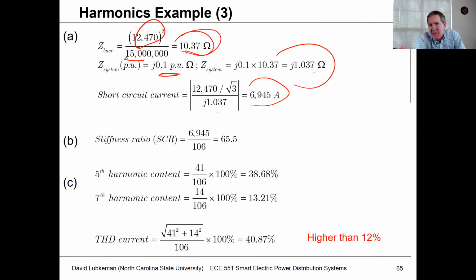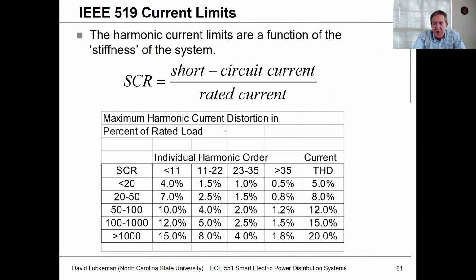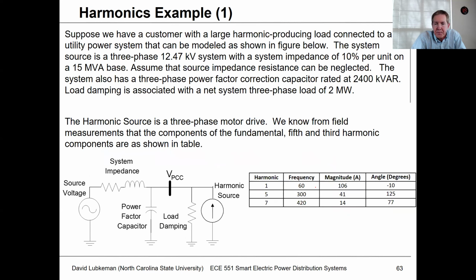So if I have a load injecting 106, the stiffness factor is this short circuit current divided by 106, which is 65.5. So whenever going into the tables to get the limits, I'm going to look at the values corresponding to 65.5, which fall into this range here. What this does is give me the limitations on the individual harmonics and the total harmonic distortion.